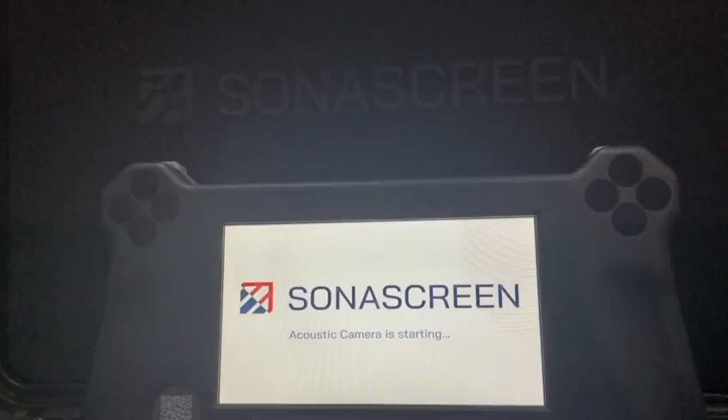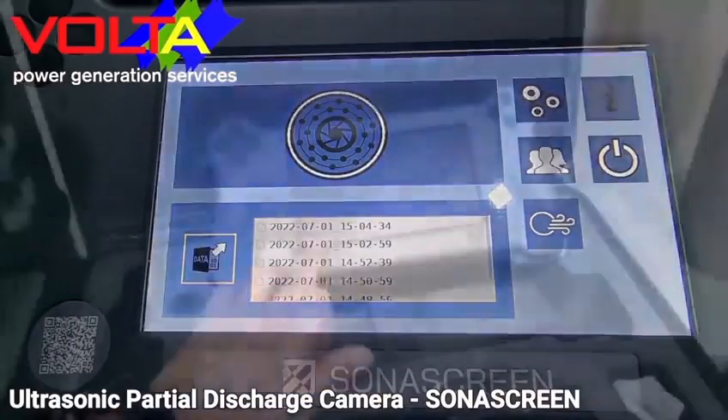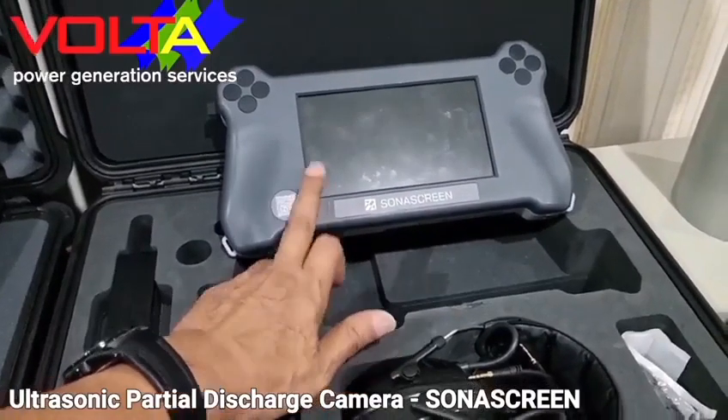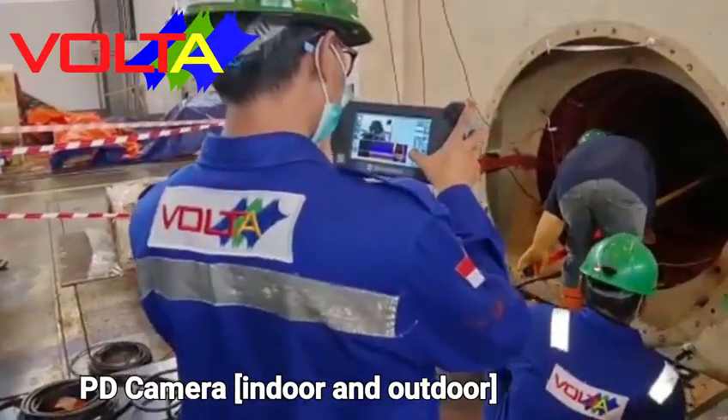The third is the SonaScreen partial discharge camera. During stator energization with an external high voltage power supply, our instrument is able to identify partial discharge activity in the stator winding visually.